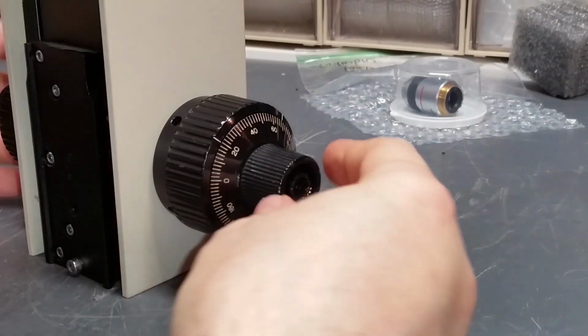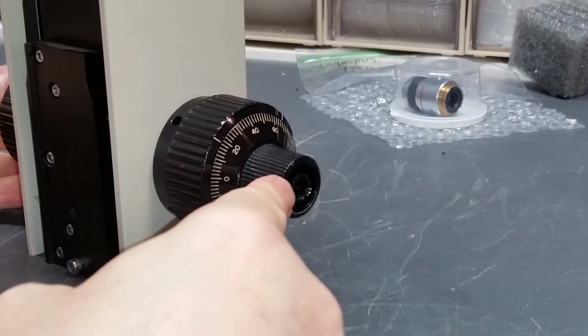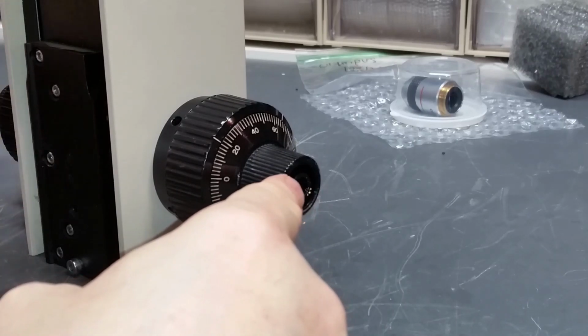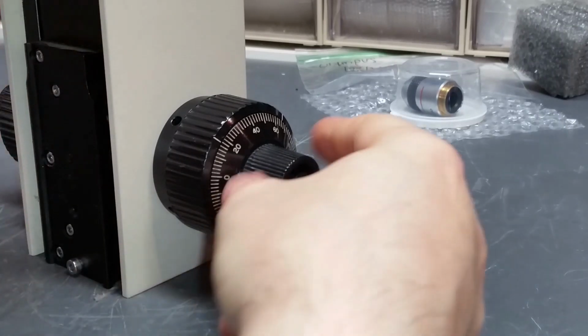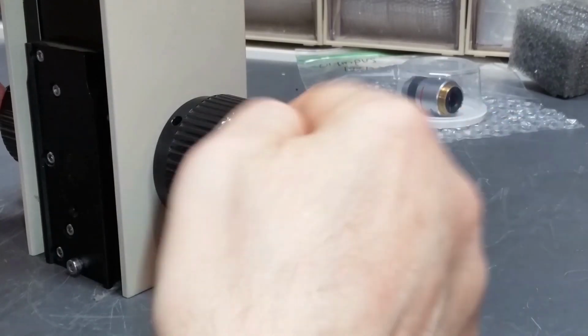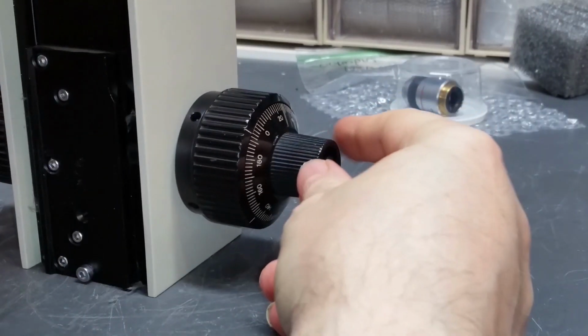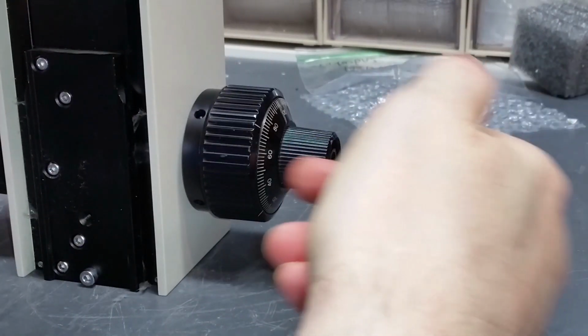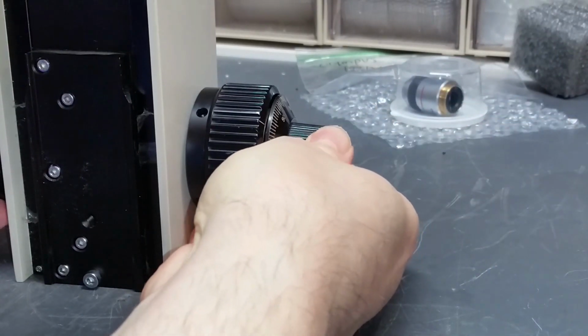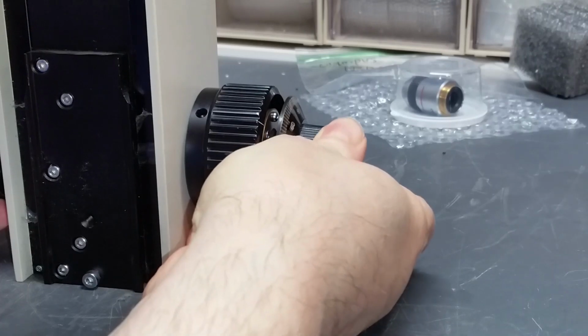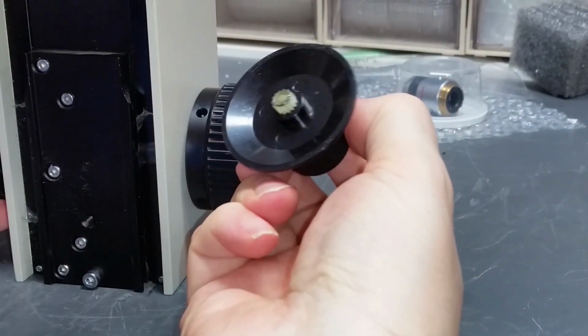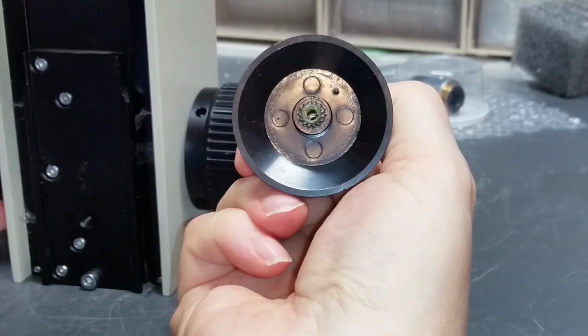And when I did that, this was the side with the screw loosened on, and that's unusual. Ordinarily, the other side loosens, but in this case, this is the screw. This is the side that's got the fine focus gear in there. And so that's the one that loosened, and that's also where the bend is at. So since that screw is out, all I've got to do to take the knob off is just carefully pull this out. At that point, the knob and the fine focus gear, as you can see, that gear is intact and seems to be in good shape.